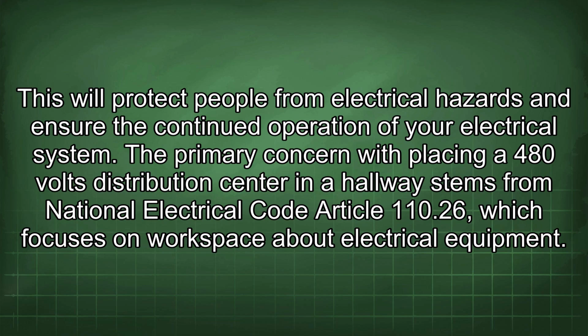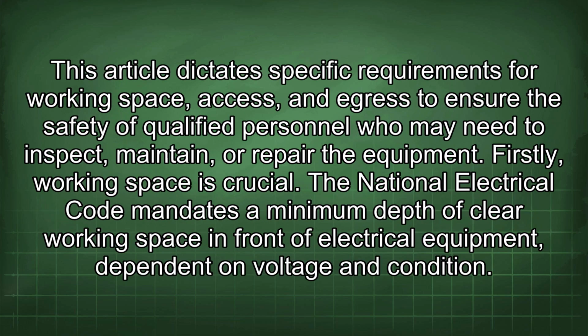The primary concern with placing a 480 volts distribution center in a hallway stems from National Electrical Code Article 110.26, which focuses on workspace about electrical equipment. This article dictates specific requirements for working space, access, and egress to ensure the safety of qualified personnel who may need to inspect, maintain, or repair the equipment.